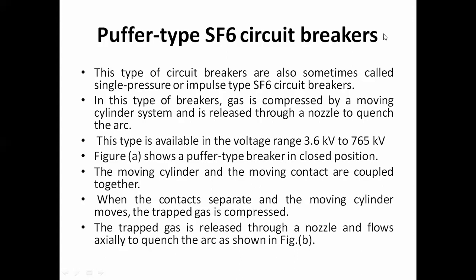In this type of circuit breaker, the gas is compressed by the moving cylinder system, and then it is released through a nozzle to quench the arc. This type of circuit breaker is used in a wide range of voltages, ranging from 3.6 kV to 765 kV. In the next slide, I will show you the pictorial view of how this circuit breaker operates. The moving cylinder and the moving contacts are coupled together. When the contacts are separated, the moving cylinder moves and the trapped gas is compressed. The trapped gas is released through a nozzle and flows to quench the arc, as shown in the figure.